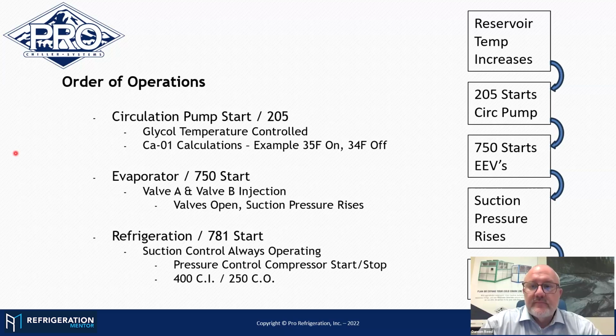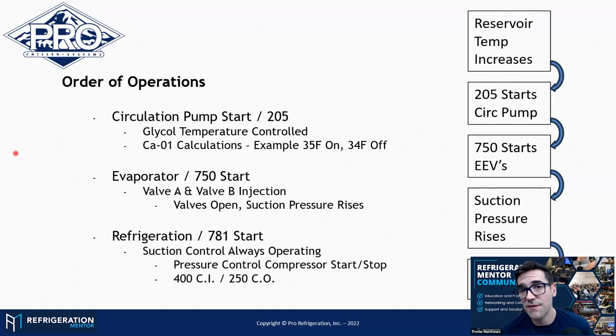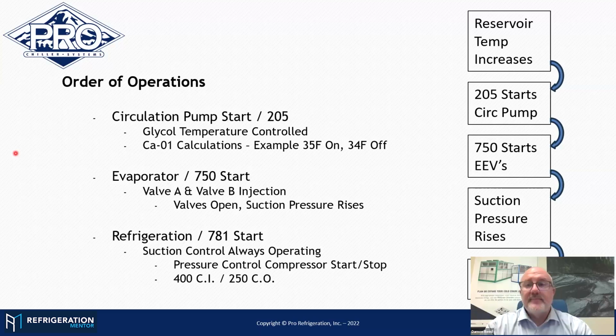That's right, because you have to go through codes and regulations. You can't just throw a CO2 system out there. And I can see the fear of CO2 dropping dramatically. After people get trained, they understand it's just another refrigeration system. It's the startup sequence of the equipment and the verification with this level of controls. It's not uncommon to spend a few hours just verifying sensors and controls before you add refrigerant to the system. With synthetic systems, we'd get as much gas in as we could and start running, and you still follow the same processes, but it's almost anticlimactic when you start that compressor on a CO2 system, because everyone's so excited and wants to hear it get up and running. Then it starts, and everyone looks at each other and says, well, that's it. Yeah, that's it. It's working.